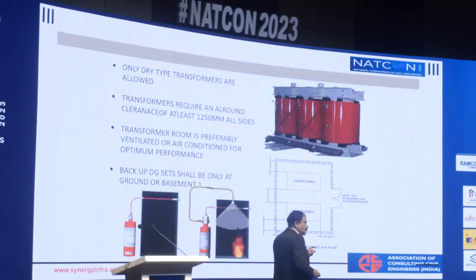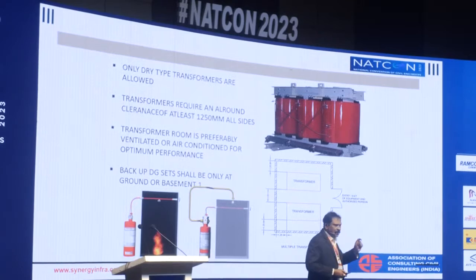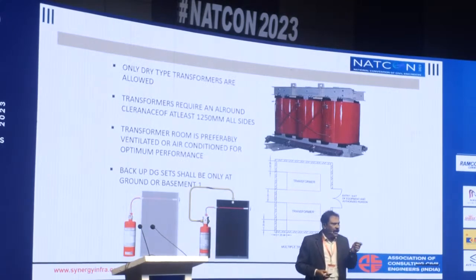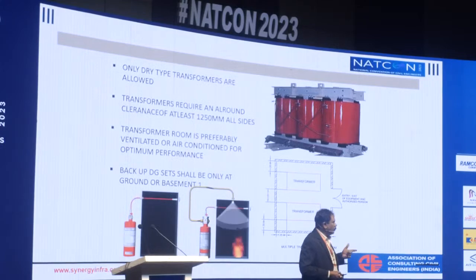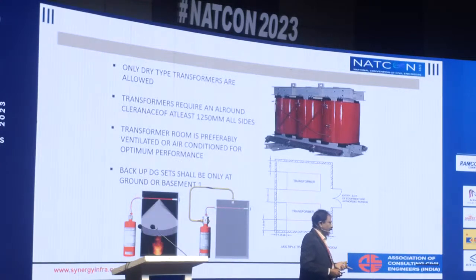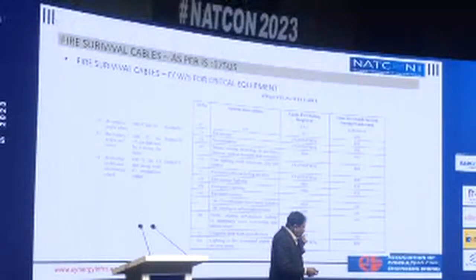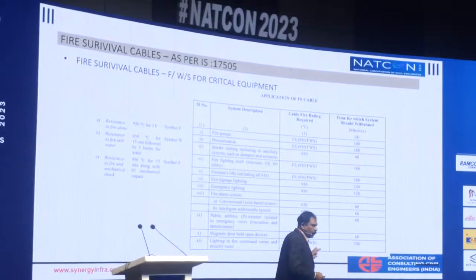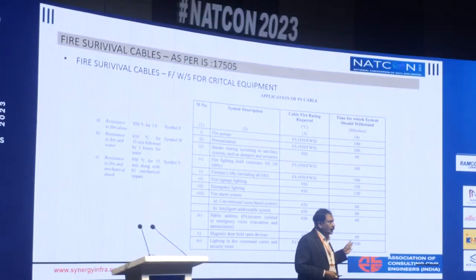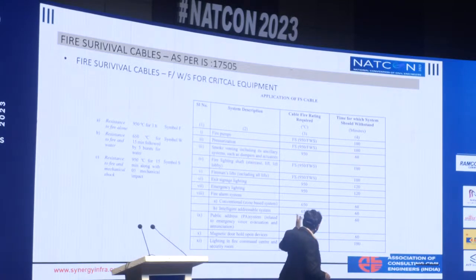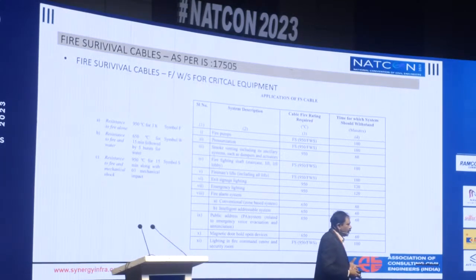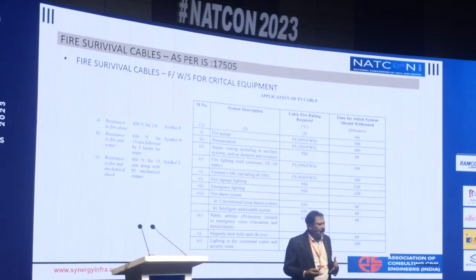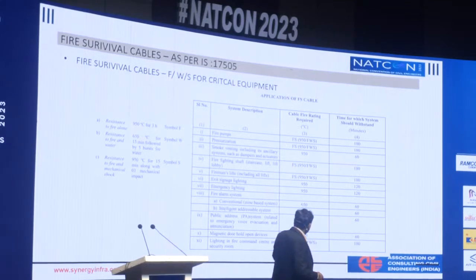So that's why the earth leakage circuit breakers are provided for 30 milliamp sensitivity, and if the leakage is around 100 milliamperes, then probably an ignition can cause a fire. So that can work like an ignition. These are some of the things, and another thing which has come out in 2021 is the type of cables which we need to use for things like fire pumps and pressurization. They're all life safety systems. Internationally, the cables are called CWZ, but in India they have introduced the terminology as FWS. So the fire pump cables, whatever we use, are for pressurization systems.